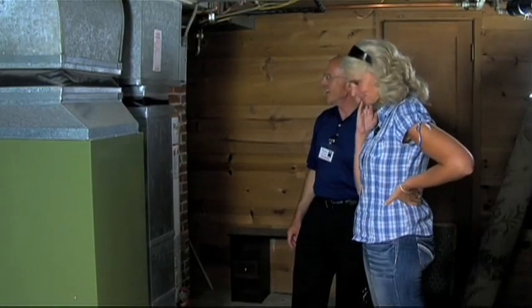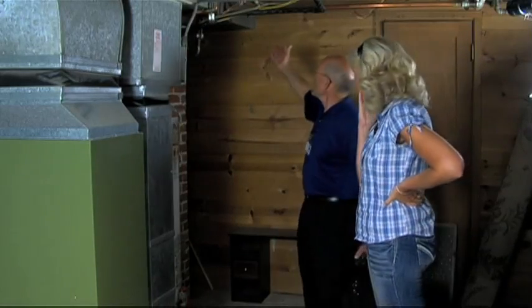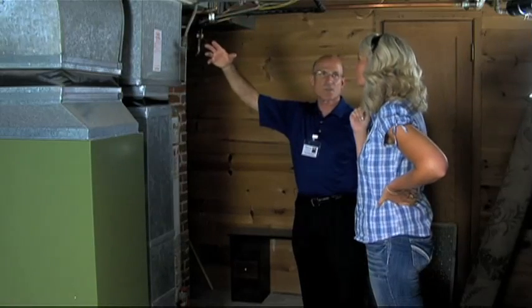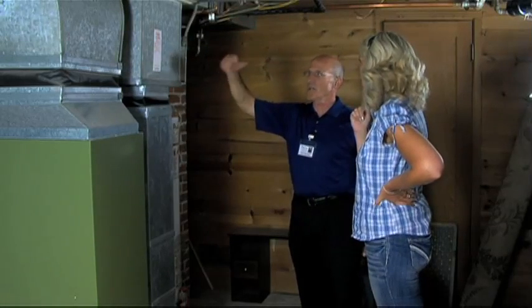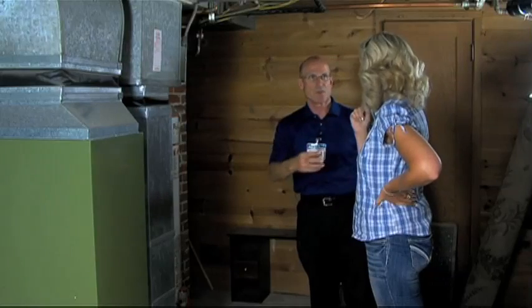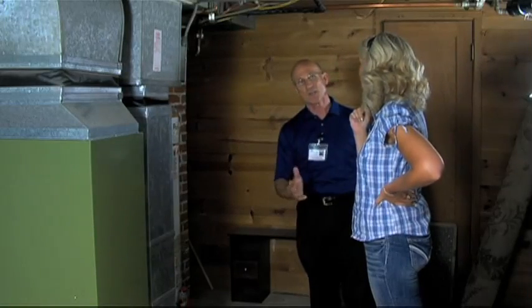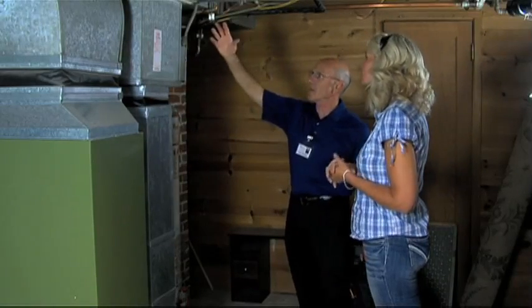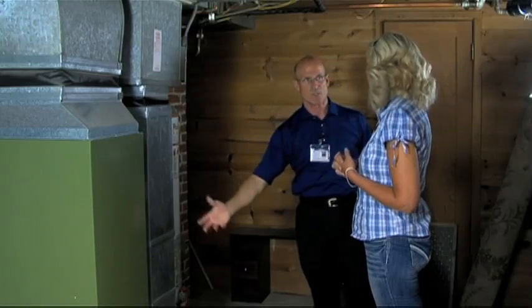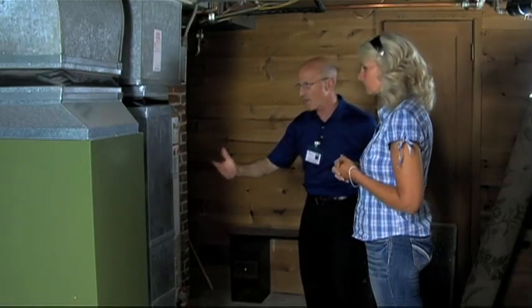Long time, yeah. So this is the air that comes back from the house, called return air. When we looked at the upstairs equipment and took that dirty filter out, that was the return air back to the equipment. And it's real important to have enough of this. Otherwise, remember, we starve the equipment, like squeezing off the straw, and that's not good.